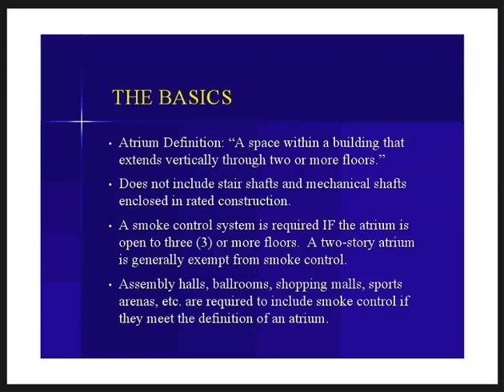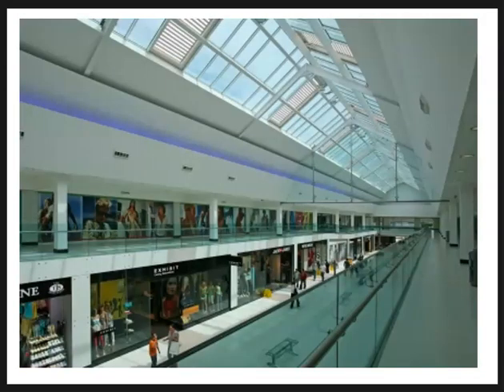So assembly halls, ballrooms, shopping malls, sports arenas, all of these kinds of places that are very large volume places are going to include smoke control if they meet the definition of an atrium, or if they have other issues that might lead us to require it. So here's a great picture of a typical covered mall. Not as popular as they used to be. Everybody likes the open air malls, the outdoor malls nowadays, but these were very popular at the end of the 20th century. And the problem is, see how it's open from first floor to second floor. There's tons of people. The exits are not necessarily spaced so close as you would in a normal building. And so as a result, they're going to require smoke control.